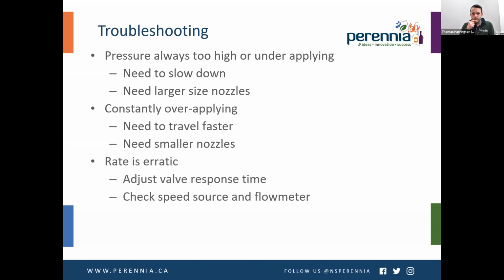The third thing on this list is if your rate is always erratic and it's bouncing around all over the place, you could need to adjust your valve response time. Especially on those throttling valves, if they're trying to make adjustments too quickly, you could have an erratic rate. So maybe you need to slow down the response time, or maybe it's not responding fast enough. You could also check your speed source and your flow meter just to make sure that your wiring and all that is intact. I've definitely seen this if you have a chafed wire that's maybe just slightly loose or something, and that could cause this erratic rate.